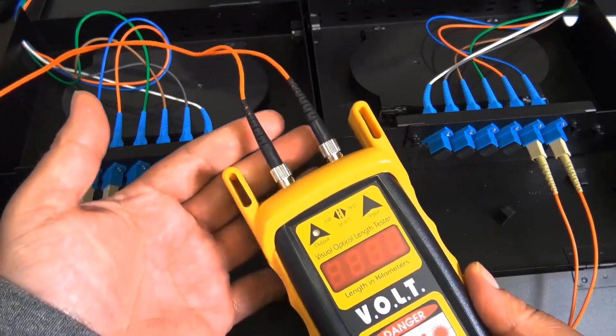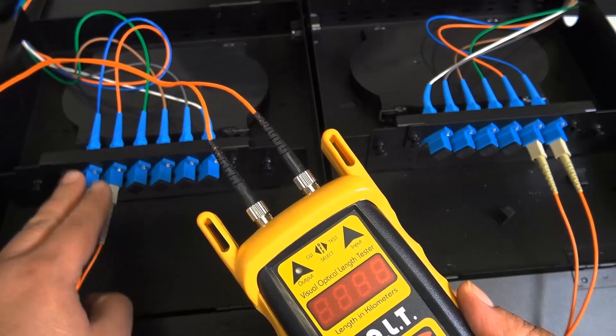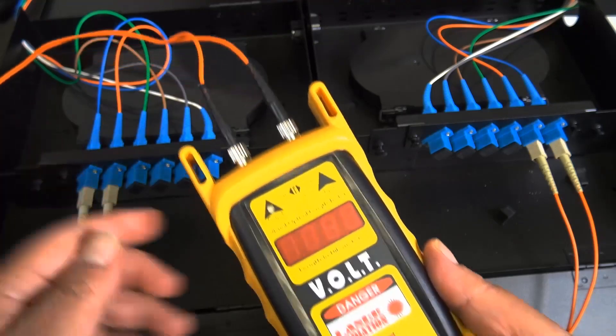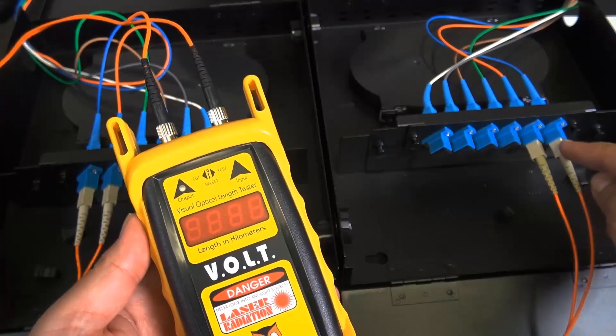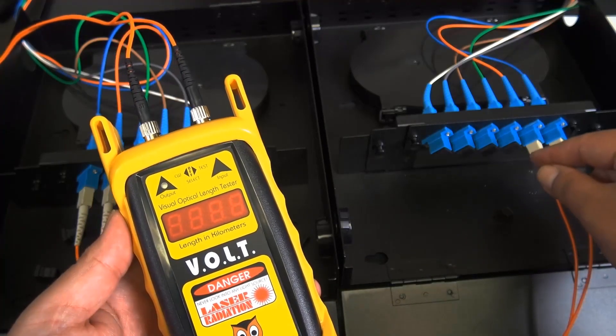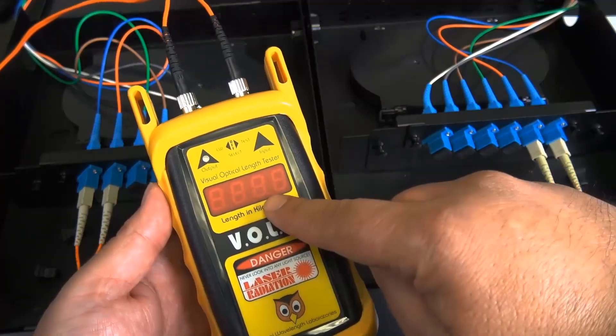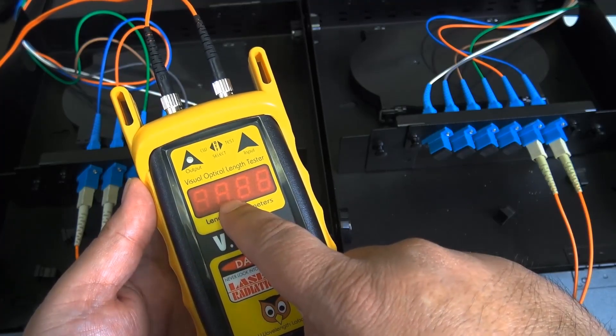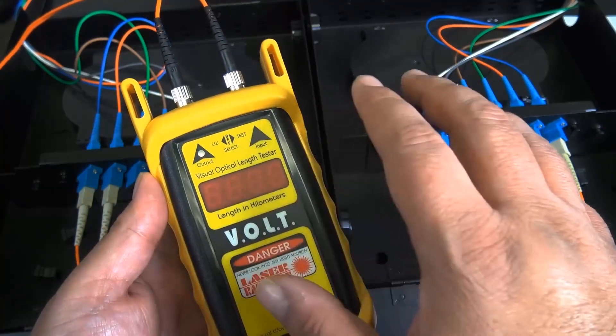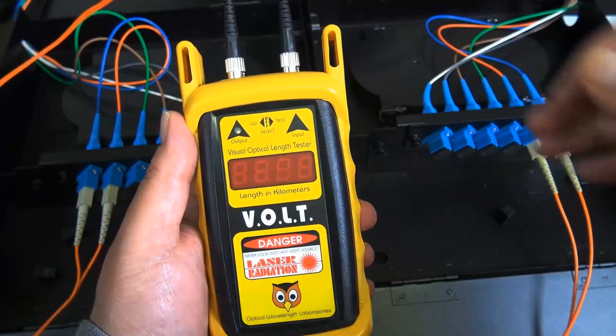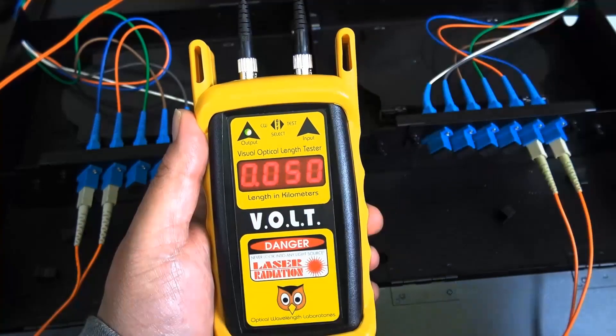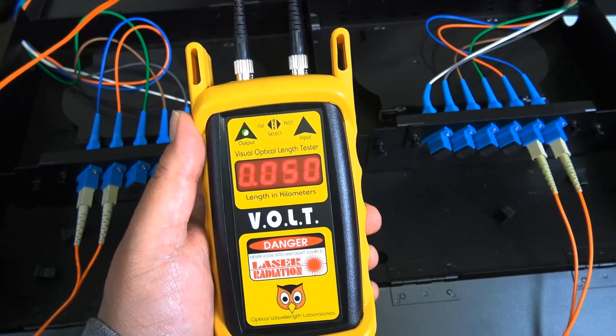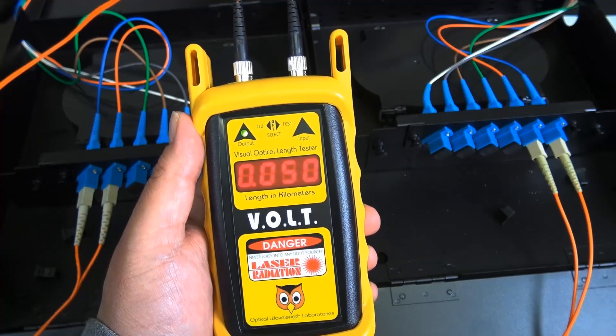Okay, so as I mentioned before, we have two strands plugged into the two strands on this side, the two ports. It's going to send a signal down one of these strands. And we have a loop back cable over here. So the signal is going to come through, just come back the other way, bam, back over the tester. It'll give us a reading right there. And we're going to take that, it tells you what the length is in kilometers. And we're going to do some math after that to figure out what our length is with this cable. Okay. Let's turn it on. Okay. So we have a .050 reading. Let's do some math.